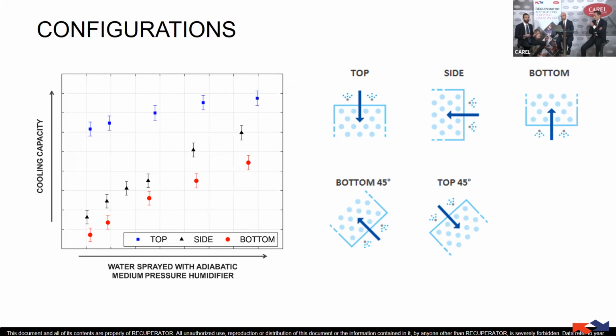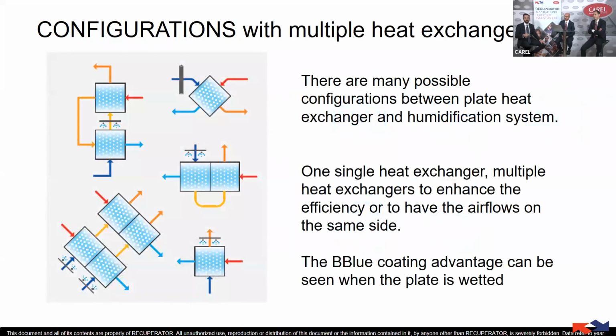Then we can have a really high cooling capacity. But if we move the humidification system to the side and then to the bottom, we decrease the cooling capacity because we are wetting the surface less. So it's really important to spray water inside and to wet the heat exchanger as much as possible. But let's think of something a little bit more complicated.